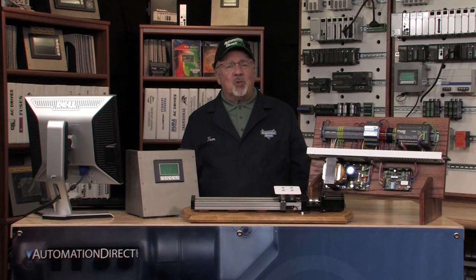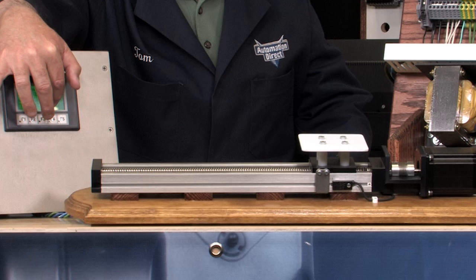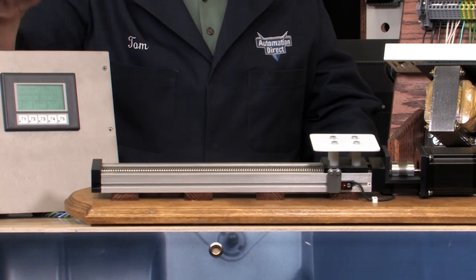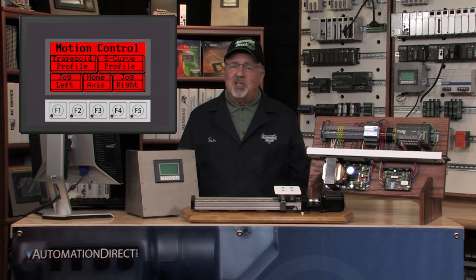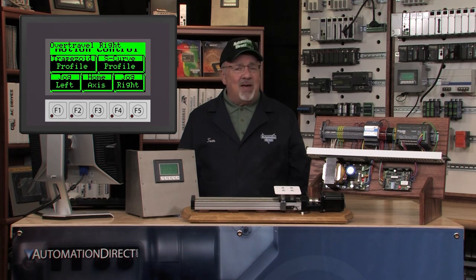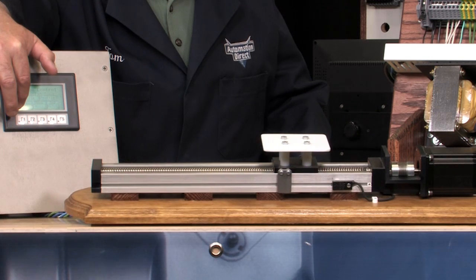Let me demonstrate the over-travel alarm conditions. I jog the slide to the right until the over-travel right proximity is actuated. The stepper motor will stop and the C-More panel will sound its internal beeper. The C-More panel's background screen will flash between green and red, and there also will be a message displayed at the top left of the panel that reads over-travel right. The alarm will continue until the problem is corrected. I jog the slide to the left so that the over-travel right proximity is no longer actuated, which clears the alarm condition.